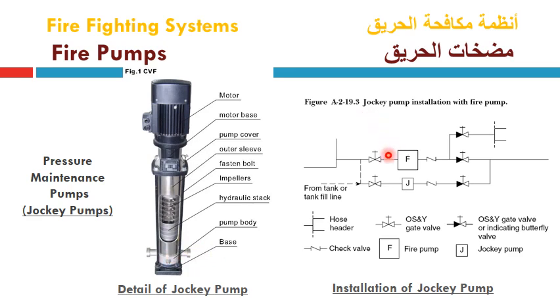Also, this figure shows how to connect the jockey pump in parallel with the main fire pump, with its isolation valve of OS and Y and non-return valve separately, and this is the main gate valve of the main pump and non-return valve, and this is the test header for the hose valves, which was discussed before in early slides of this lecture.